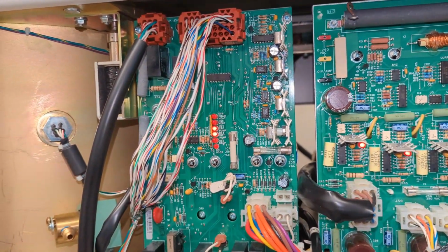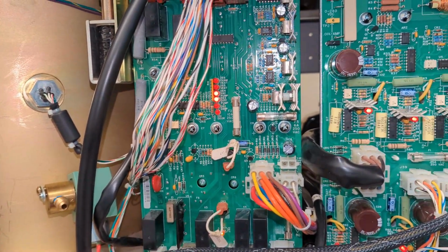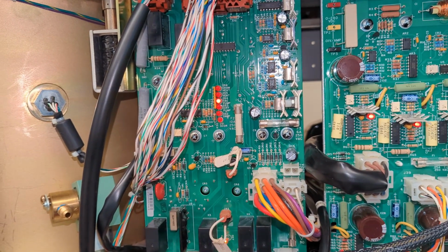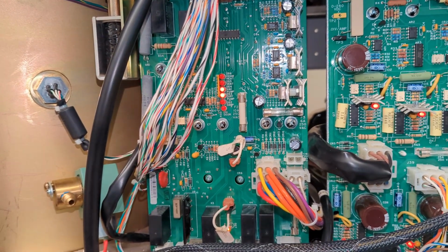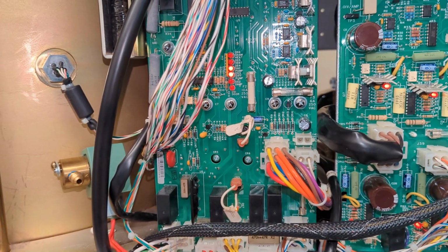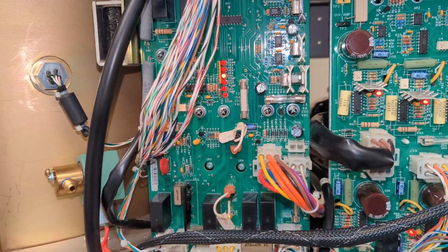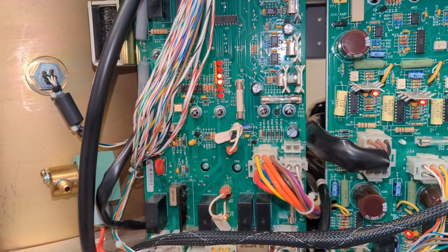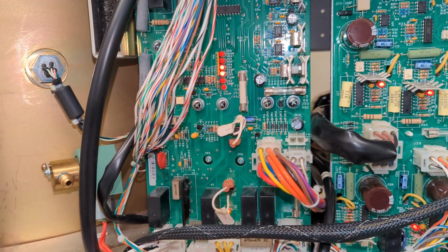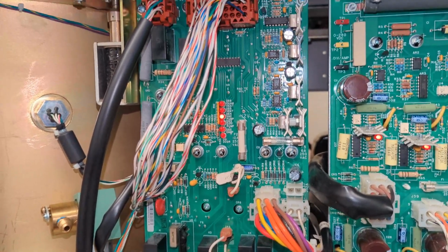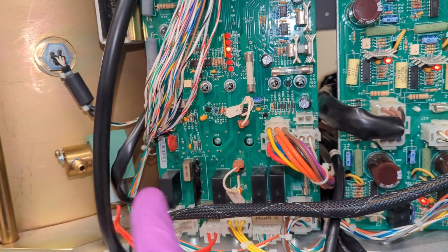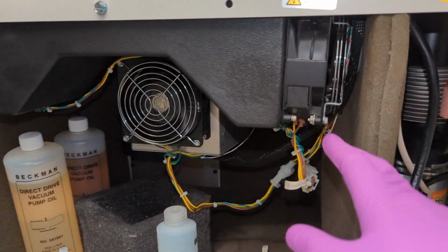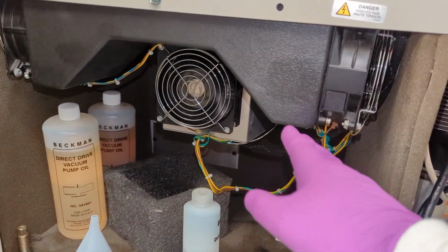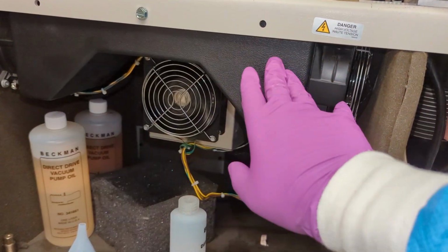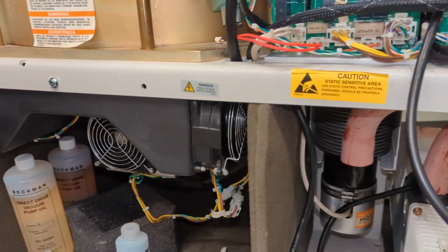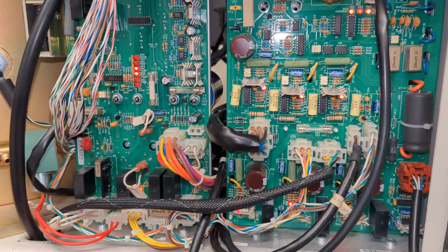All right. So here is the other board that's driving some of the other high power peripherals, such as the vacuum pump, the Peltier thermoelectric module to heat and cool the chamber, door switch, vent solenoid, diffusion pump. So that is all being controlled via this board. You can see that you've got the big relays here, and you can't really see it, but you've got some cooling fans here. The Peltier module basically sits in this area. But we can take a look at the back really quick as well.